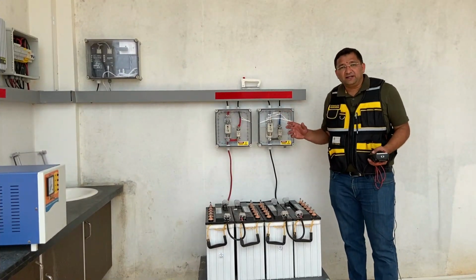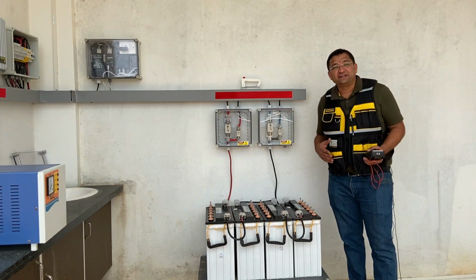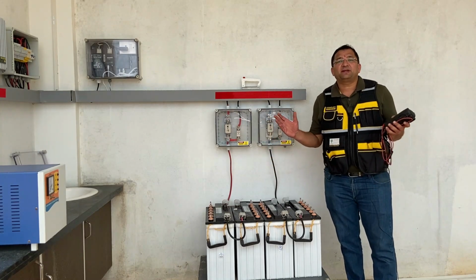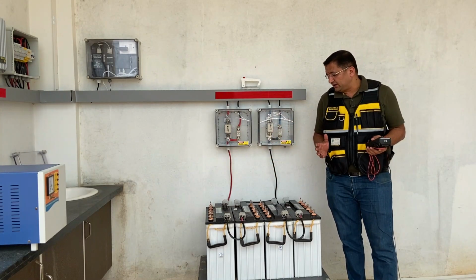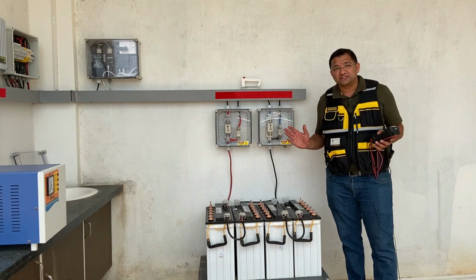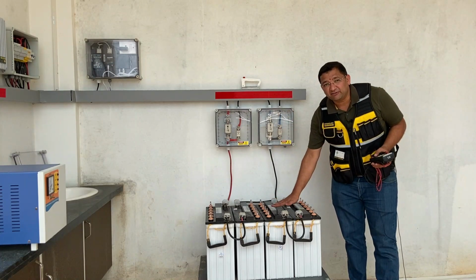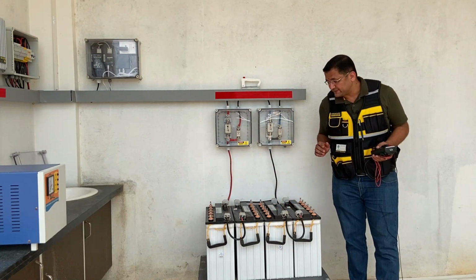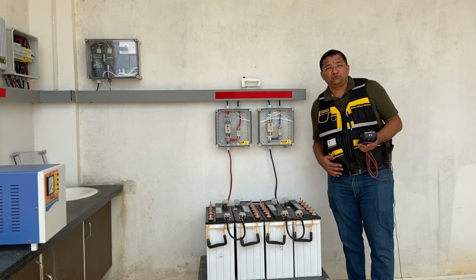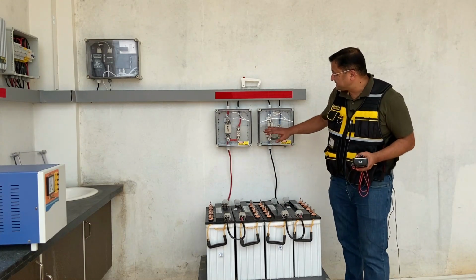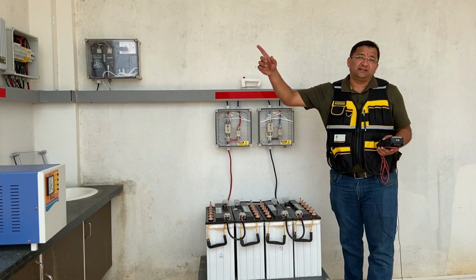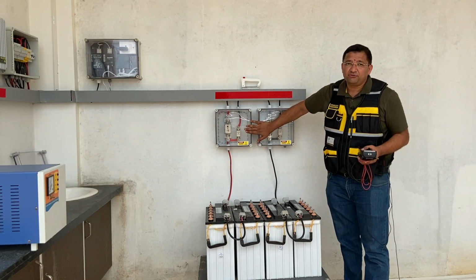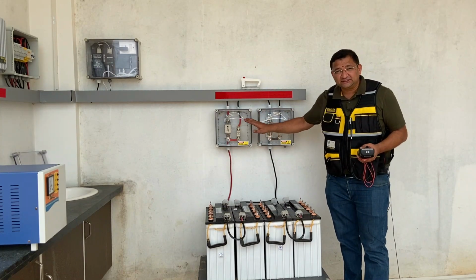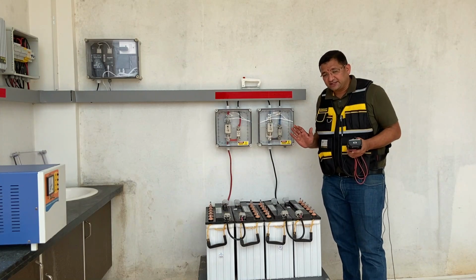So this is the next part of the DC wiring. This system can take 48 volts of battery, that is the system voltage is 48 volts. So these are our 4 batteries connected in series. This gives 12 into 4, 48 volts, and this is connected into our charge controller and the inverter through these fuse boxes.